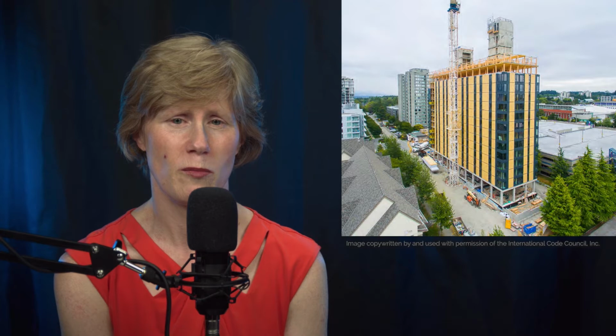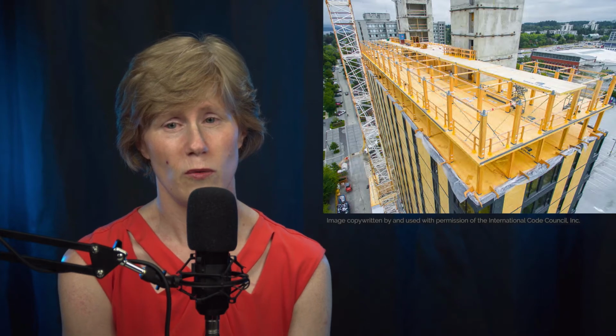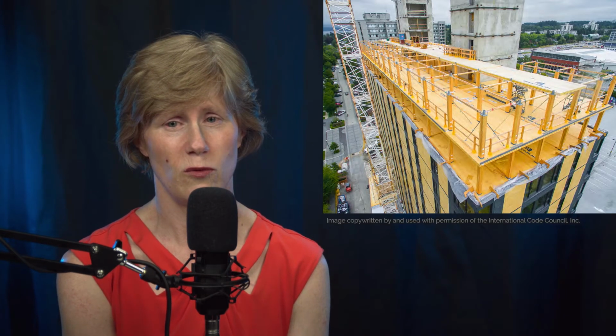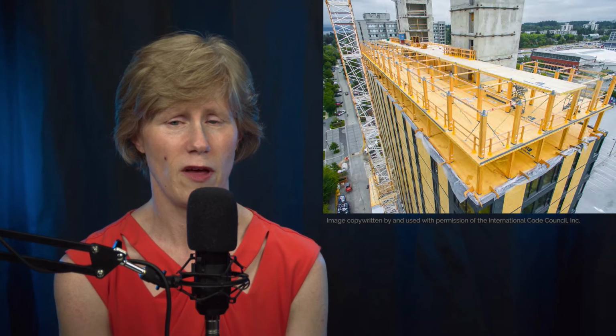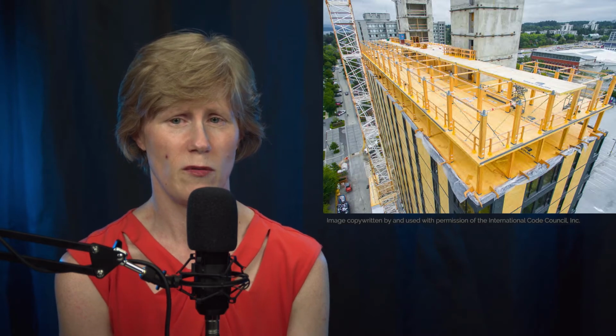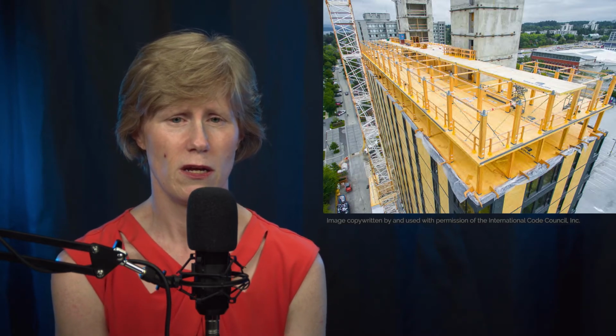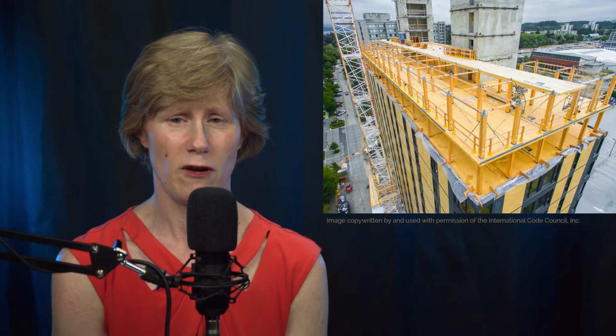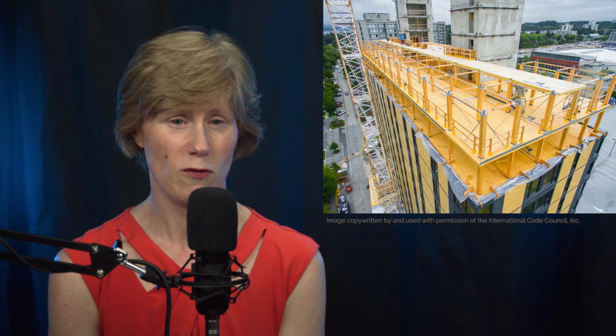Under the 2021 Building Code, this would have to be classified as Type 4A construction because of the height of the building. When we're talking about Type 4A construction, we're looking at encapsulating all of that mass timber with gypsum with at least a 3-hour rating. And it's up to the designer. They can choose to have more exposure of the structural elements, such as the picture on the screen now, which would be a Type 4C application where the structural elements can be completely exposed.